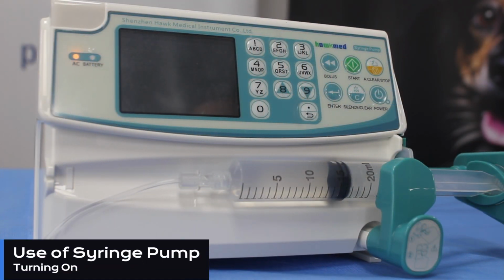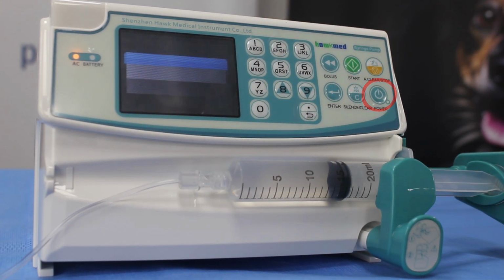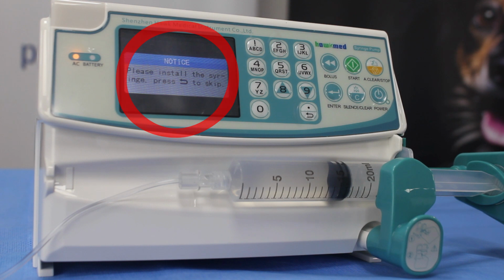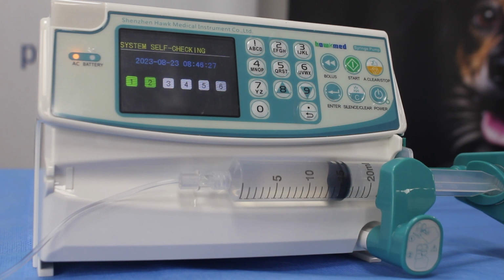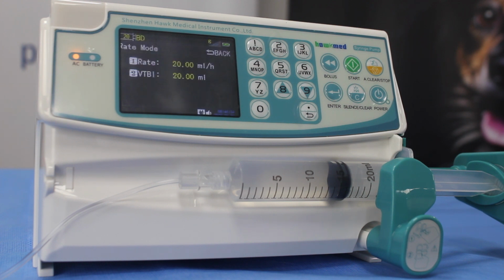To turn on our syringe pump, we can hold down the power button. You'll first have this notice appear on your screen asking you to install the syringe. We've already done that here, and you can also choose to skip this step if you're looking to just set up the pump for your patient later and install the syringe when you're ready. We can use the back arrow to get past this message. The unit will then perform a system self-check, just running through a series of beeps and illuminating our LED light in the corner. The pump has entered the rate mode. Your pump will always start on the previously selected mode setting that you've been using.